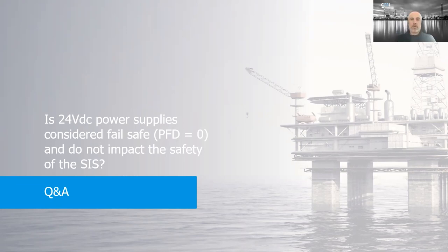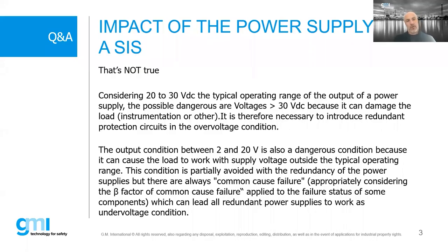Is 24 volt DC power supplies considered fail safe and do not impact the safety of the SIS? So I repeat again this point. This is not true, of course. The typical operating range is between 20 and 30 volts. That is the normal output for a power supply. It can be 24, 26, sometimes 28. The dangerous failures are voltages higher than 30 volts because this can really damage the load. So for protecting against this high voltage, it is very important to have a redundant protection circuit for the overvoltage condition. And the output between 2 and 20 volts is also dangerous because this can cause the load to work outside the range and have some malfunctions. This condition is also avoided with the redundancy of the power supplies. If you have two redundant power supplies, of course, if one goes down, the other will continue steady at 24 volts. But there are also the common cause failures that Massimo already highlighted.